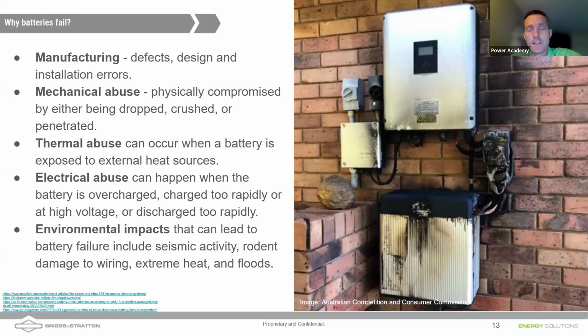One of the common things I see is a switch that's just melted or burned. Not appropriately torquing down your connections results in what we call contact resistance. If you're not applying the appropriate pressure on battery cabling, or using fine stranded battery cabling and not putting ferrules on it to transfer the electrons from that copper into the next conductor in the chain, that can be a location where heat builds up. That contact resistance is a place where electricity turns into heat.